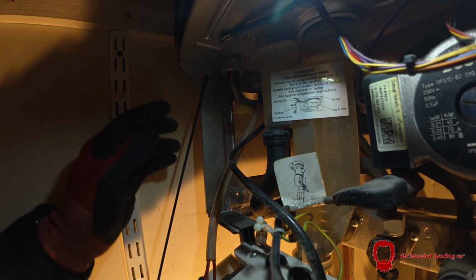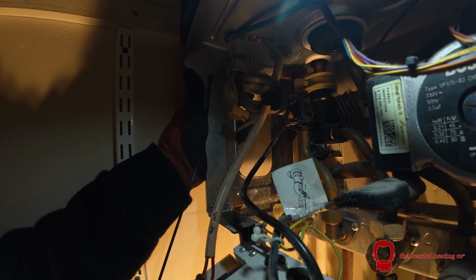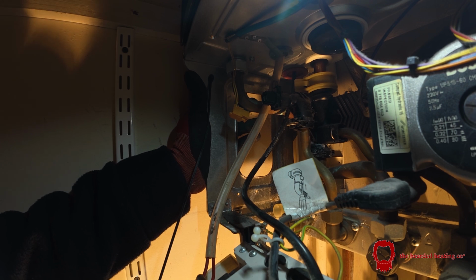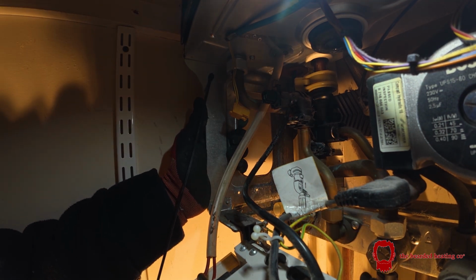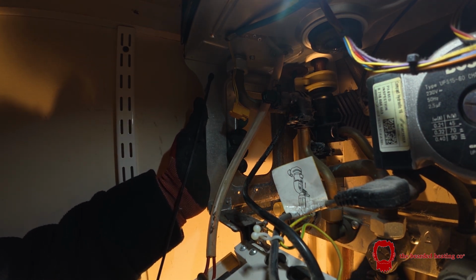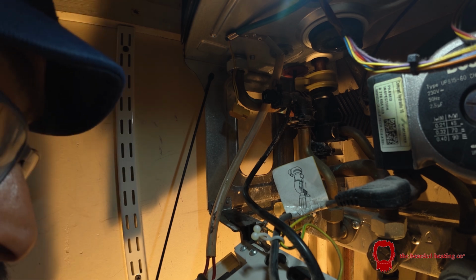First things first, let's undo the temperature sensor, the hot water temperature sensor, and move the condense out the way. Let's isolate the flow and return under the boiler. That's it, all isolated. Might as well do the gas while you're at it. And yes, straight away that water's stopping.